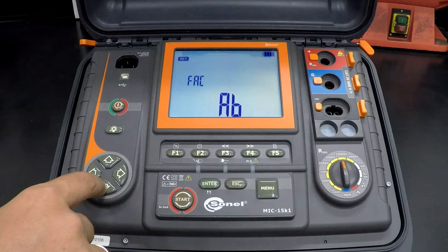Each of them changes the set of times T1, T2 and T3 to their default values. For DAR, T1 is 15 seconds and T2 is 60 seconds, and in the case of PI, T1 is 30 seconds by default, T2 is 60 seconds by default, and T3 is 0.